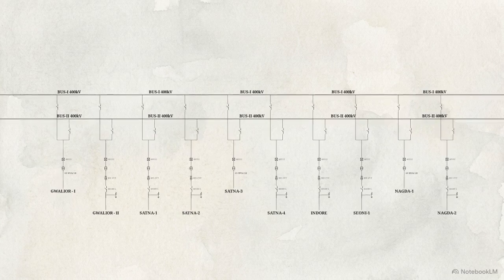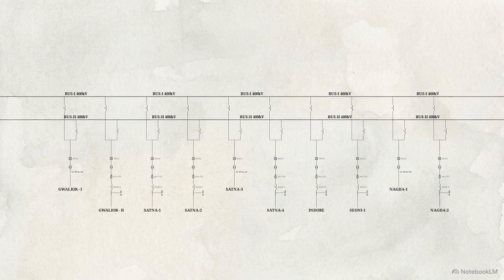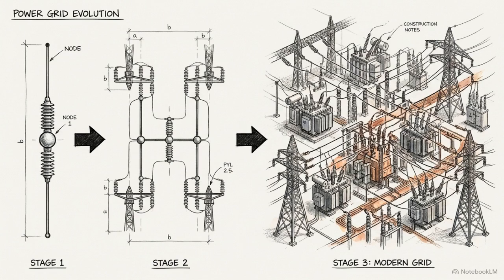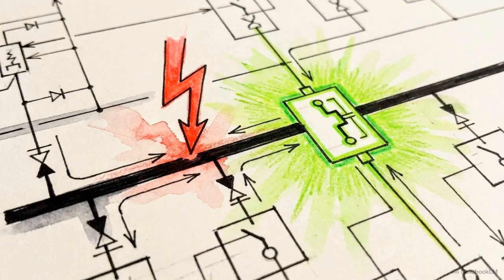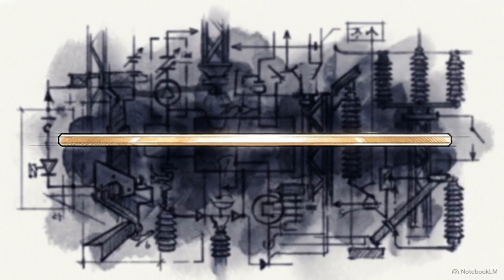When applied to a real-world, highly complex node, like the 400 kilovolt Bina substation in India, these symbols combine at a massive scale. The overwhelming complexity of this specific 400 kV schematic is the direct result of an evolutionary, step-by-step optimization process. Every breaker and line is placed to defeat the statistical fault threats we just observed. By stripping this dense diagram down to its foundational elements, the underlying mathematical logic of grid survival becomes entirely clear.